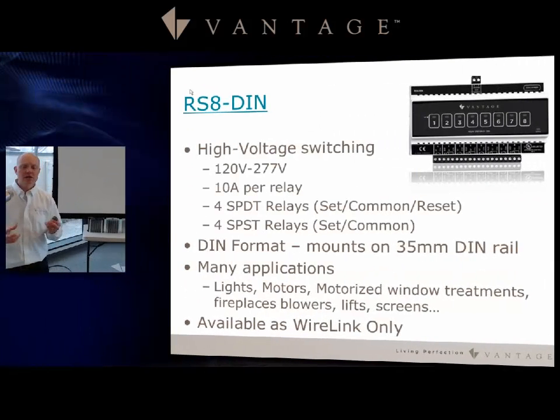The RS8-DIN is a high voltage relay device with up to 10 amps per relay and eight total relays. Four of them have set/common/reset capability for lighting, and four are specifically for motors and similar loads. If you need even more relay capacity for lights, Vantage sells a dedicated relay module for that purpose. This device is WireLink only, and applications include fireplace blowers, lifts, and motorized screens.